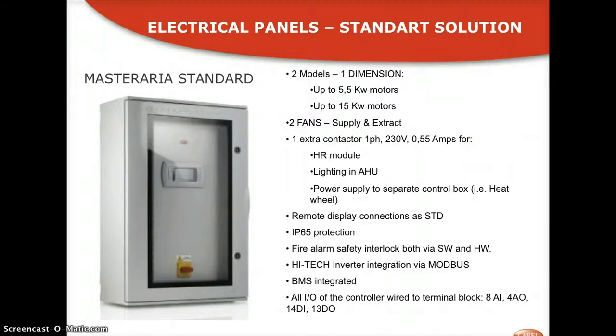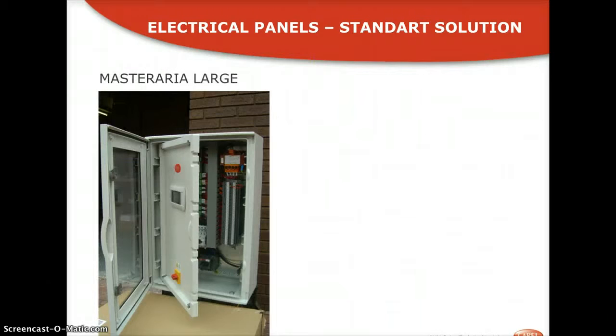It features a pCO3 medium controller which can give you 8 analog inputs, 4 analog outputs. So it's a fairly decent large controller for a typical standard air handling unit. It features also a transformer. The panel has got a double door, like all the Masteraria panels.